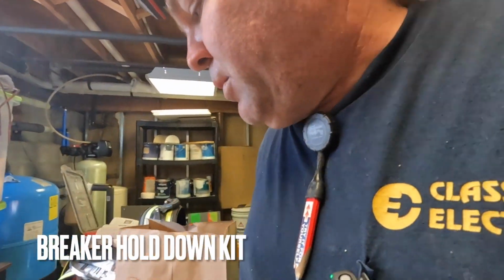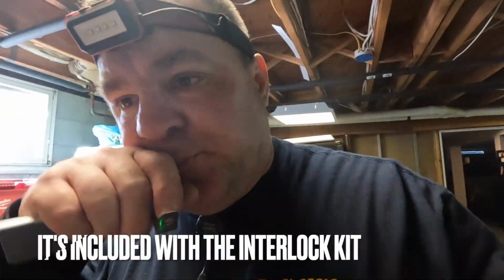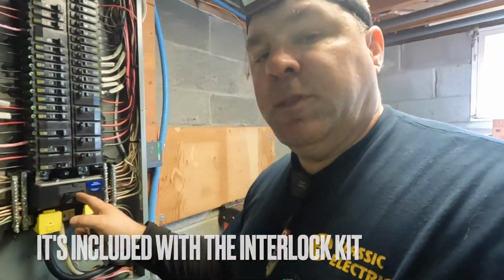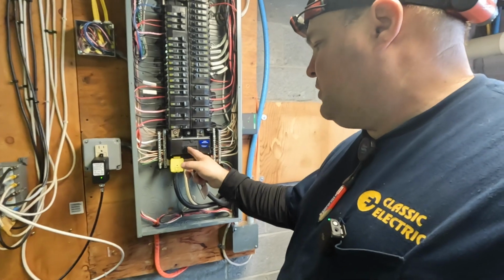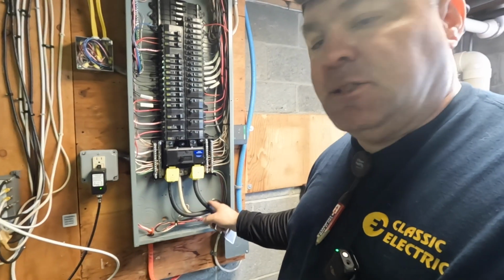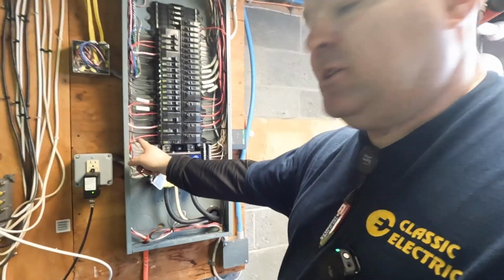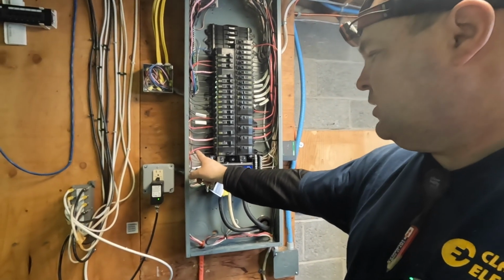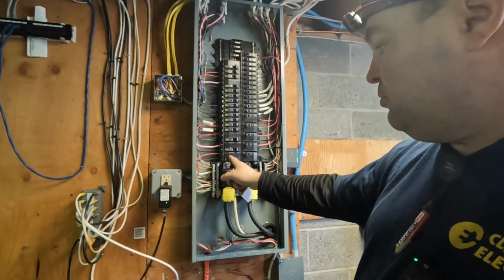We need to put in the tie down. So what we are doing is essentially back feeding the panel, okay? Right now, the main utility is the power source, okay? That's these conductors right here. This is the generator connection that I installed this morning, and I'll show you that branch circuit in a minute. And here's the portable generator wiring circuit.